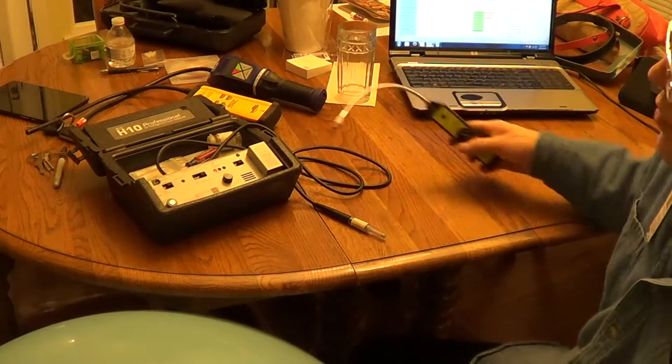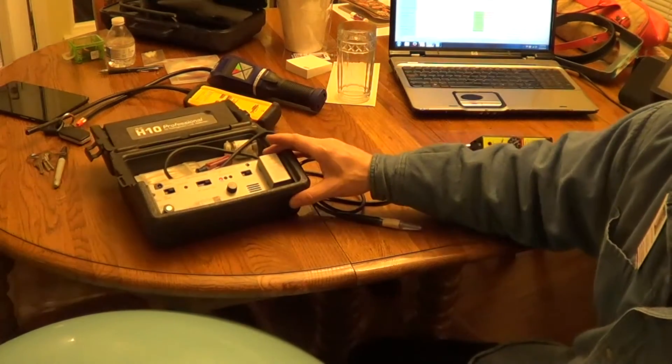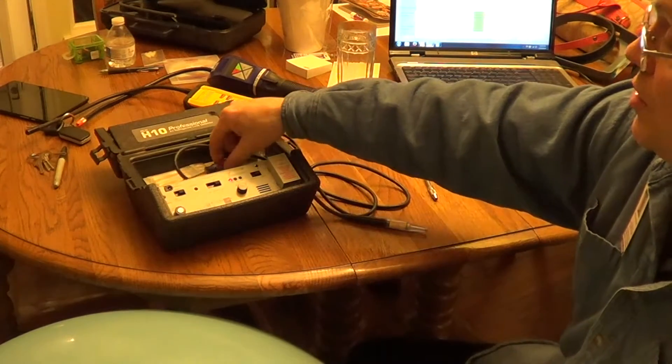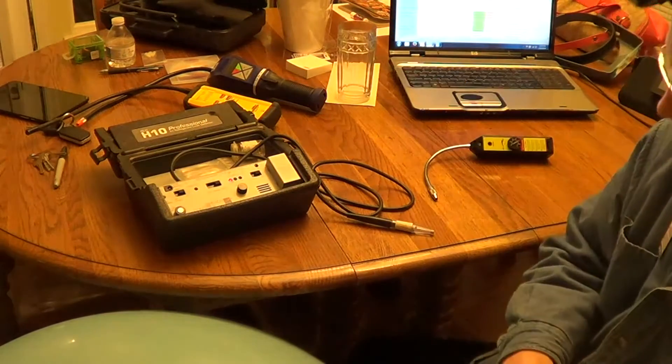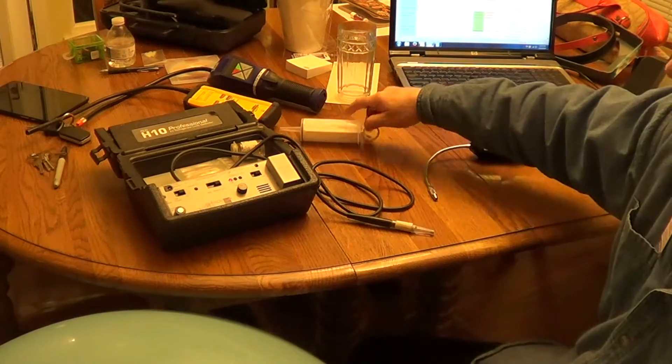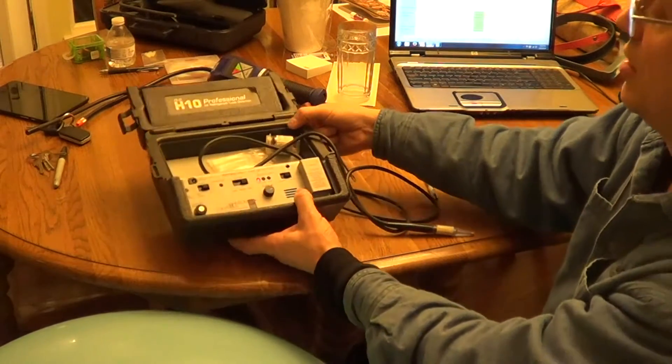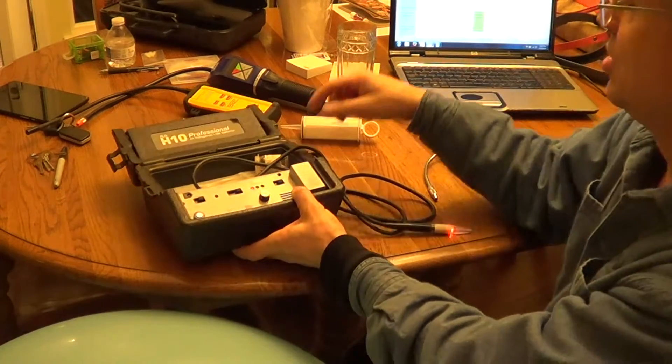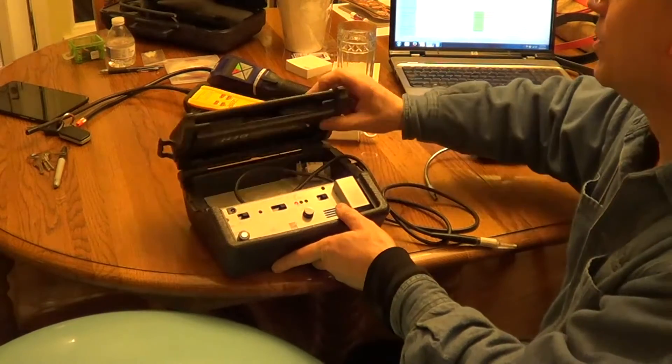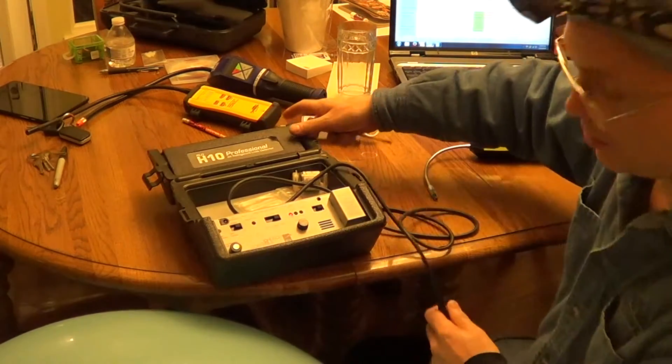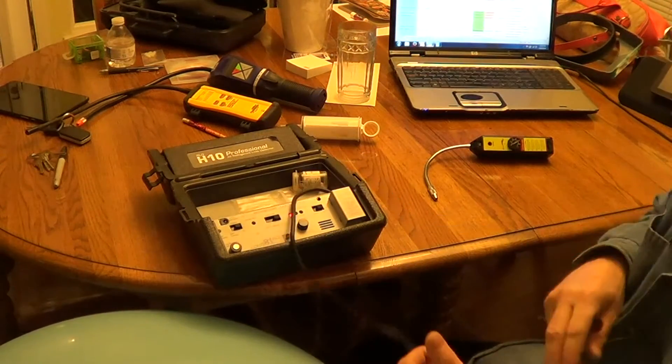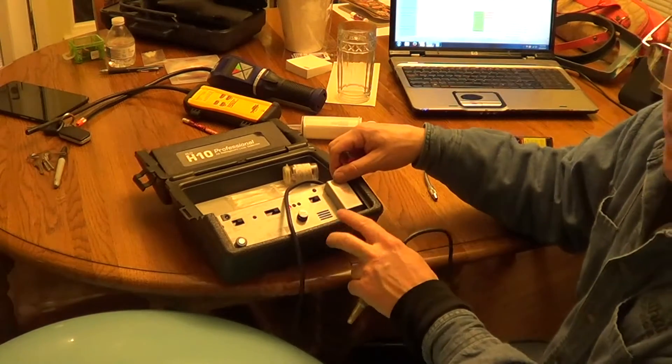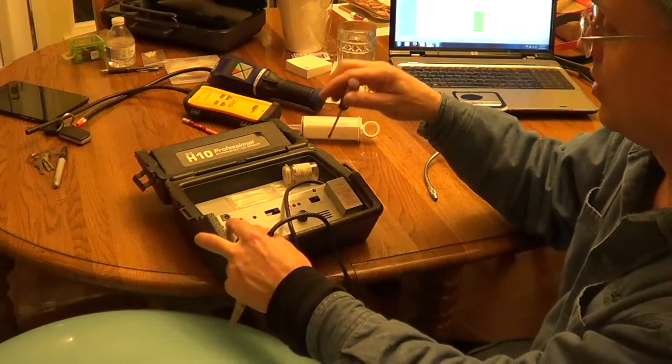Now, if you want to use the H10 for R410A, you have to run that sensor really hot. And when you do that, you can get down to about 5 parts per million sensitivity. So basically you have to ignore what the setup is. You run that sensor as hot as possible, but you're only going to get a few hours of life out of it. And if you get any large hits, your sensor will be destroyed in one hit.